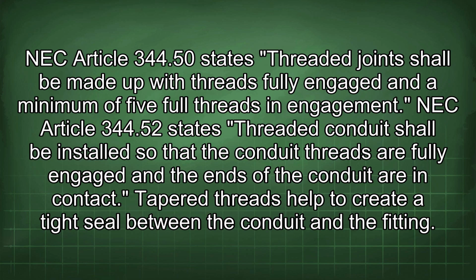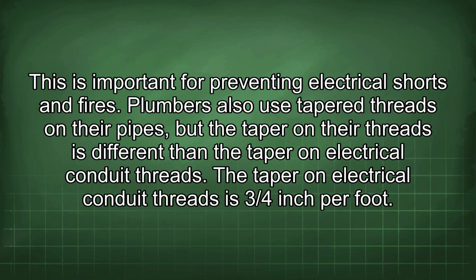engagement. NEC Article 344.52 states threaded conduit shall be installed so that the conduit threads are fully engaged and the ends of the conduit are in contact. Tapered threads help to create a tight seal between the conduit and the fitting. This is important for preventing electrical shorts and fires.